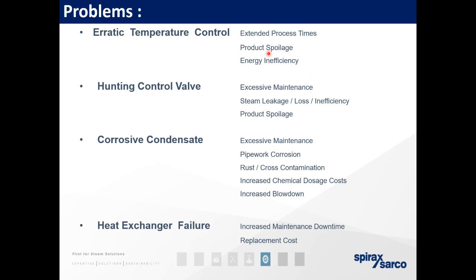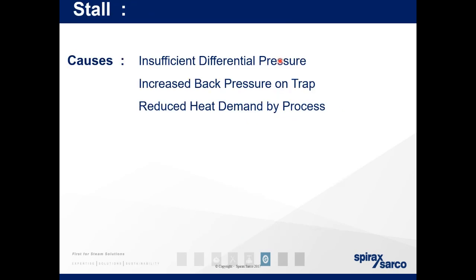Corrosive condensate leads to excessive maintenance, pipework corrosion, rust, cross-contamination, increased chemical dosage costs because you then have to remove that contamination, and increased blowdown. And as we touched upon earlier, heat exchanger failure, increased maintenance downtime, replacement costs. So causes can be insufficient differential pressure, so what you have on your inlet coming to your outlet. I will touch back on that in a second. Increased back pressure on the trap and reduced heat demand by the process.